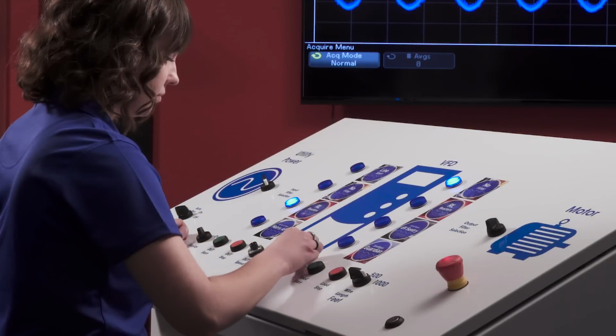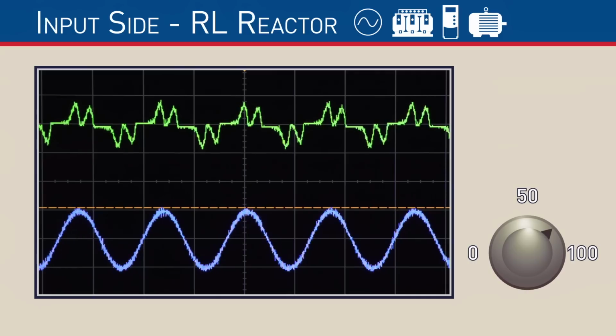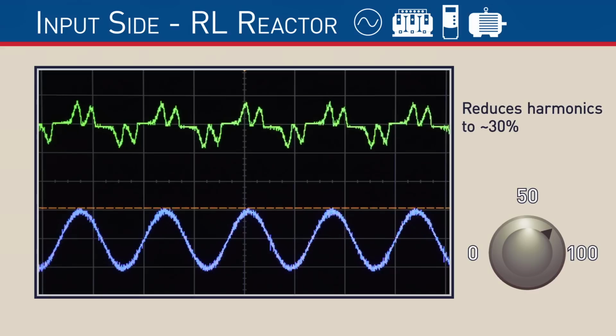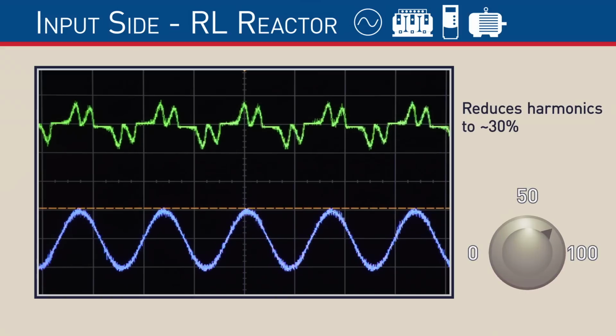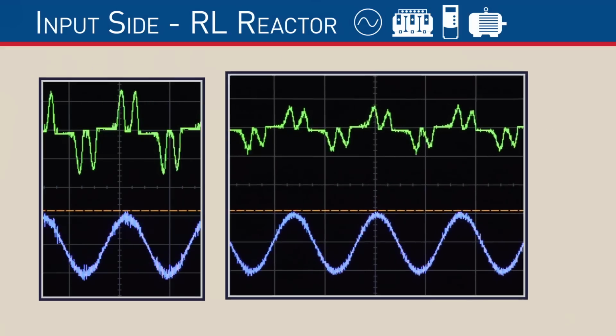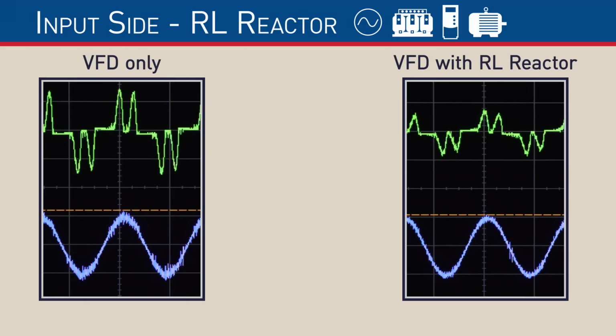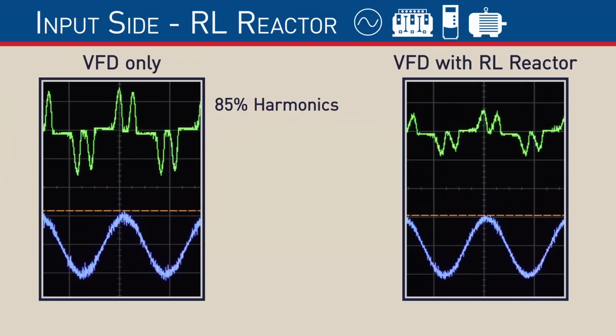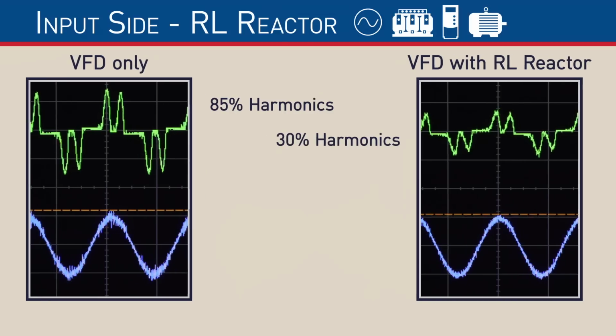As we increase the load to 75%, the current is no longer discontinuous. It is not a perfect sine wave yet, but we've taken a big step in reducing the harmonic distortion. An RL reactor can typically reduce harmonics to around 30%. We've already reviewed how a standard VFD application can create 85% or more of harmonic content, and that an RL reactor can reduce that level to around 30%.